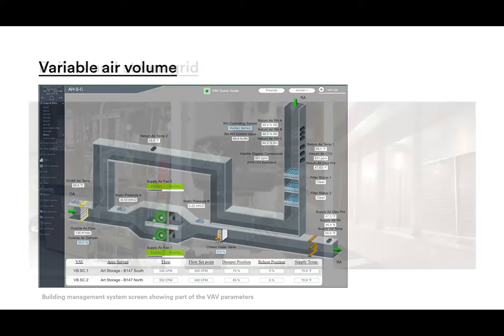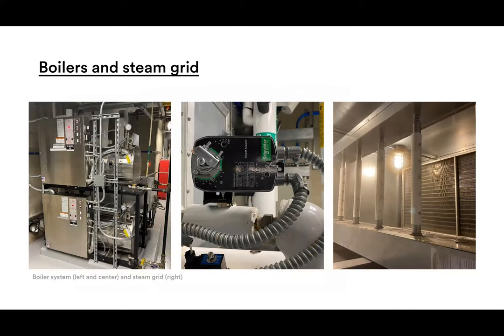Most recently, we've just finished implementing another energy conservation measure focusing on our humidification system. We increase our humidity in an area, mainly during the winter, using clean steam electric boilers. We have four 40 kilowatt boilers. These units are by far the largest consumer of energy on our entire campus. In the winter, when humidification season is at its peak, these four boilers use more than 50% of the total electricity consumed by our pavilion's building. It was clear to us that if we can introduce additional efficiency into this system, we could save a lot of energy.